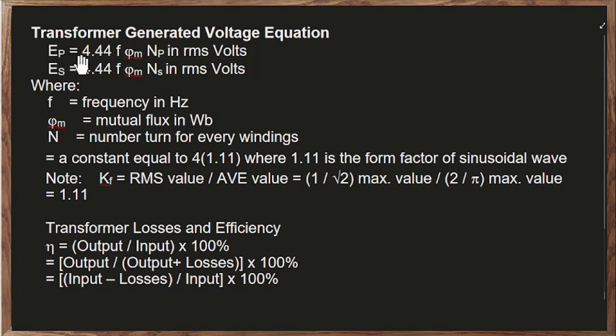Transformer generated voltage equation. So ito yung equation when we are going to solve for the primary and the secondary voltage. So we have 4.44. F is our frequency, which is in hertz. Phi sub m is the mutual flux in Weber. Then our voltage must be the RMS voltage. So ang lalabas dito is the RMS voltage. Yung itong 4.44, this is taken from 4 times 1.11, so that is the form factor of the sinusoidal wave. Kasi AC wave yung kinukonsider natin when it comes to transformer.